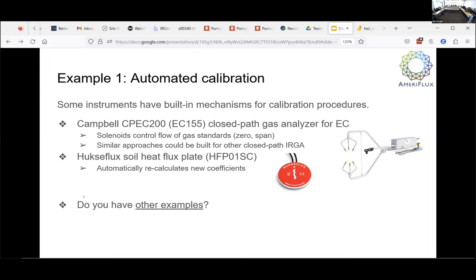Well, the other point to that question, though, with the LI-7500s, in our calibration history, most of the errors just come from somebody making a mistake when they calibrate it, rather than the sensor being bad. So there's that. That's why I only do it for 7500s at the Great Lakes sites. I don't touch them. If you calibrate all the time, you have to be really, really good at it. Because in our experience, a lot of the errors we have in our data is because something went wrong when somebody calibrated something. So that's a great point.